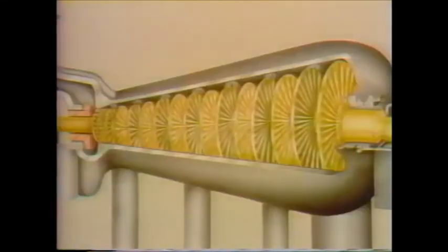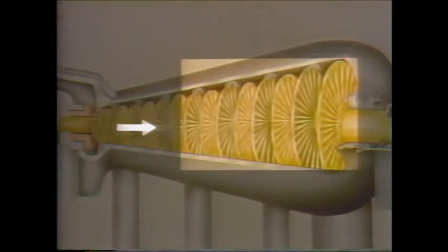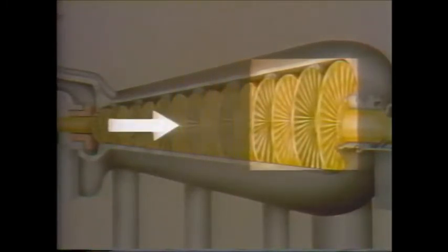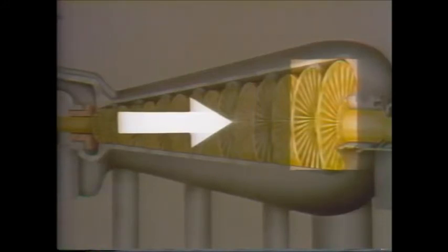In simple terms, we can say that pressure produces a pushing force and vacuum a pulling force or suction. The creation of a vacuum in the last stages of a turbine helps the turbine operate more efficiently. Pressure varies inside a turbine depending on load. At low loads, many of the later stages in a turbine may be under a vacuum. As load is increased, more and more of these stages start to operate under pressure. And finally, at full load, only the last few stages of the turbine may actually be under a vacuum.